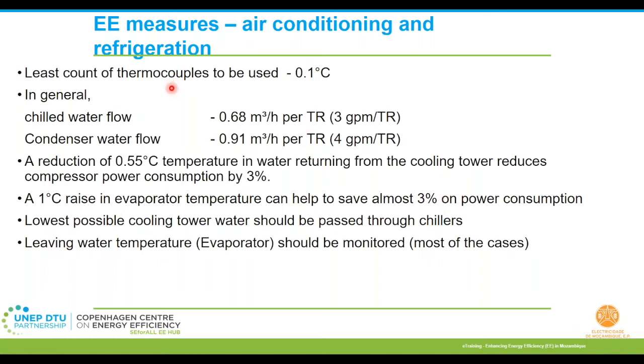So in general, the design would be the flow requirements for chilled water, condenser water. This would be the design requirements. That is about 0.68 meter cube per hour for every TR water is required.